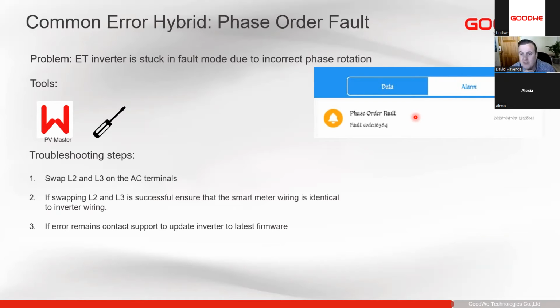Changing the phase order doesn't really affect anyone, but it can affect the three-phase inverters because they are sensitive to phase rotation, to make sure that anything on the output has the correct phase rotation. So normally you'll see it stuck in a fault mode. SEMS portal might report this as VAC FAC failure, but you can always see the fault code on site, that 16384. That is phase order fault.